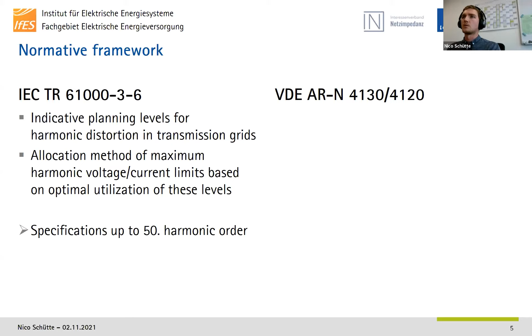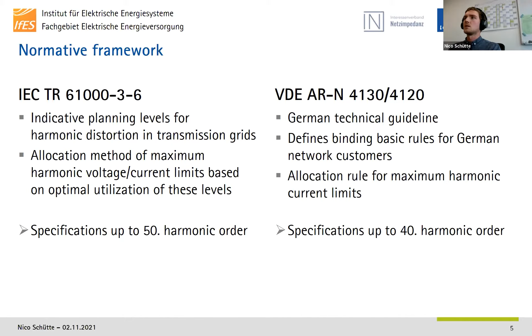The other guideline is the German one, introduced by VDE with number 4130 for extra high voltage level, and the same for high voltage level, which is 4120. It defines binding basic rules for German network customers. This means there is some flexibility for users, but it's mandatory to respect these basic rules. It also provides the allocation rule for maximum harmonic current limits, and these specifications are made up to 40th harmonic order. So as I said, we're focusing on a frequency range up to 2 or 2.5 kilohertz.